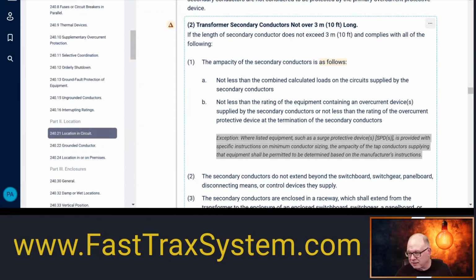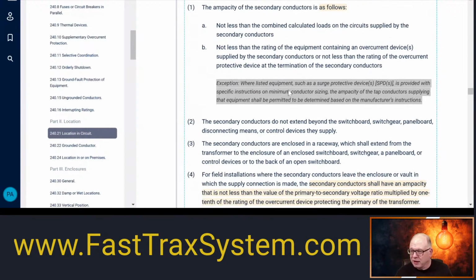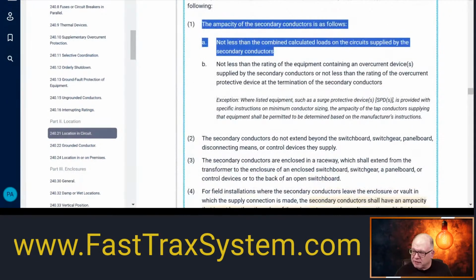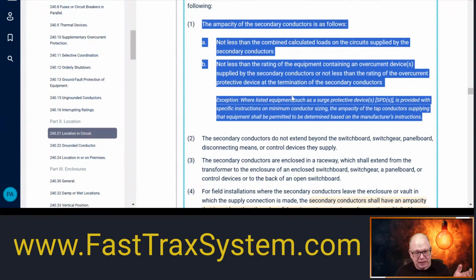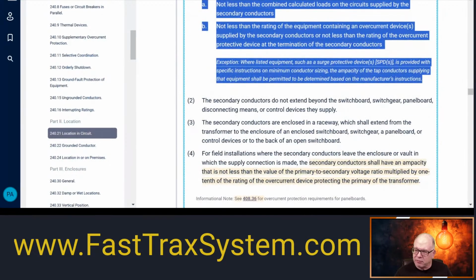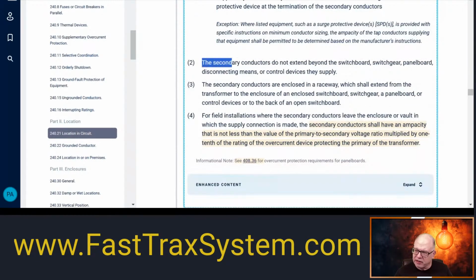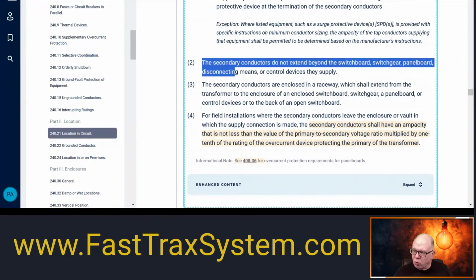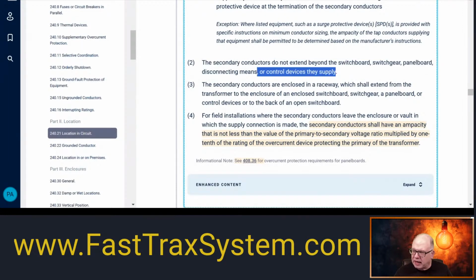All right, let's get back to the lesson here. Let's make sure we at least finish this today. All right, so we know what our ampacity, our secondary conductors, a minimum have to be, and we know what size they have to be to handle the calculated load. And whatever the panel is that we're installing, then we're making sure that those conductors are equal to or greater than the rating of the device that it terminates into. We got that. So the next caveat we have to meet is that those secondary conductors do not extend beyond the switchboard, switchgear, panel board, in our case, disconnecting means or control devices they supply.